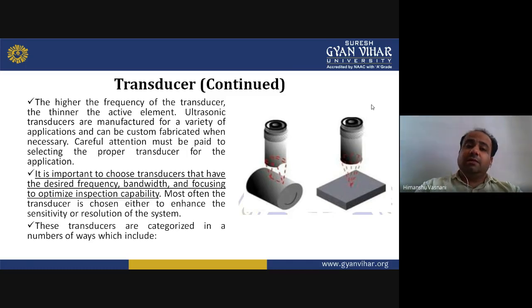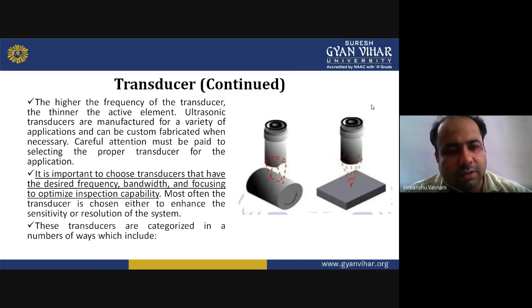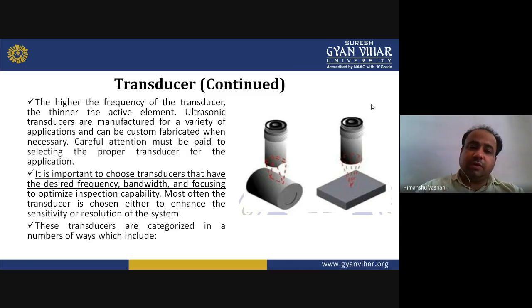Ultrasonic transducers are manufactured for a variety of applications and can be custom fabricated when necessary. Careful attention must be paid to selecting the proper transducers for the applications. It is important to choose a transducer that has the desired frequency for the application we are using. So it is important to choose a transducer that has the desired frequency, bandwidth, and focusing to optimize inspection capability. Most often, the transducer is chosen either to enhance the sensitivity or the resolution of the system.